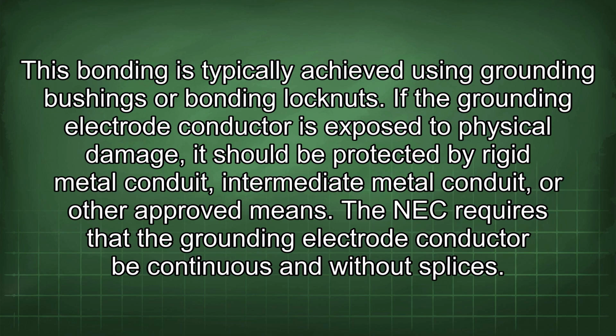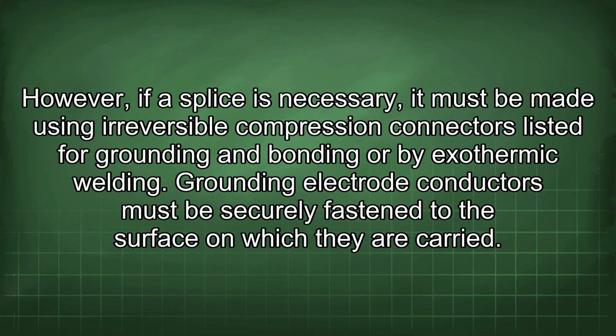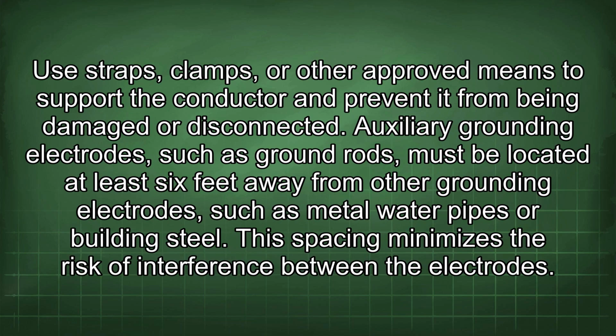The NEC requires that the grounding electrode conductor be continuous and without splices. However, if a splice is necessary, it must be made using irreversible compression connectors listed for grounding, or by exothermic welding. Grounding electrode conductors must be securely fastened to the surface on which they are carried. Use straps, clamps, or other approved means to support the conductor and prevent it from being damaged or disconnected.